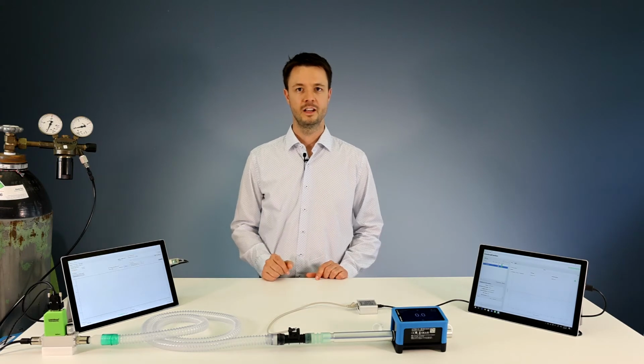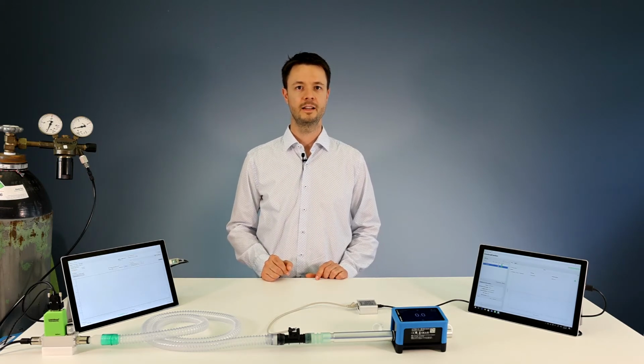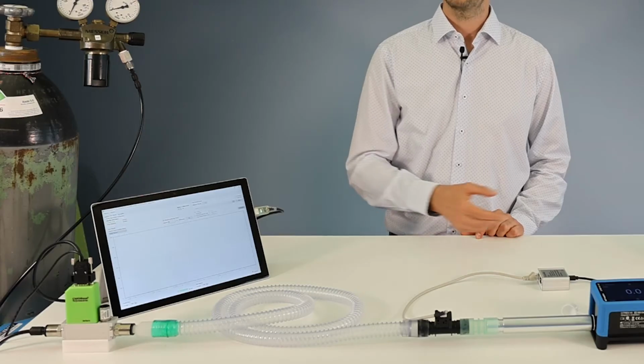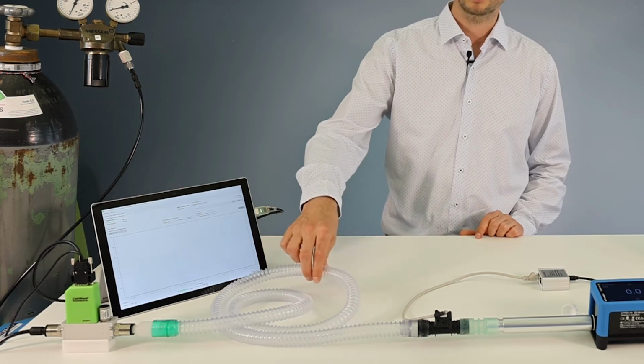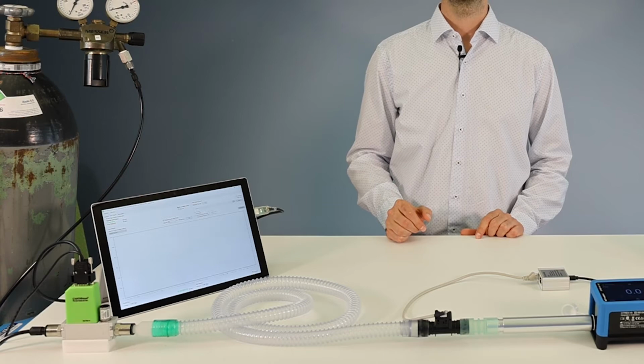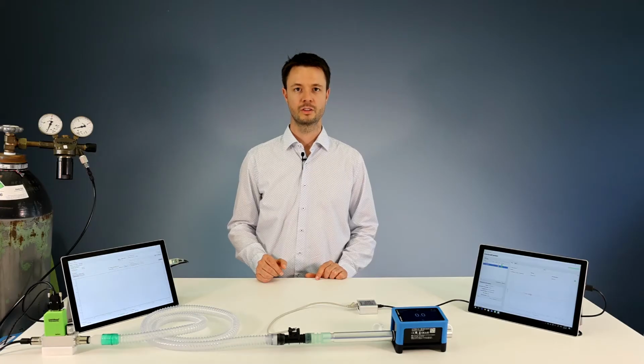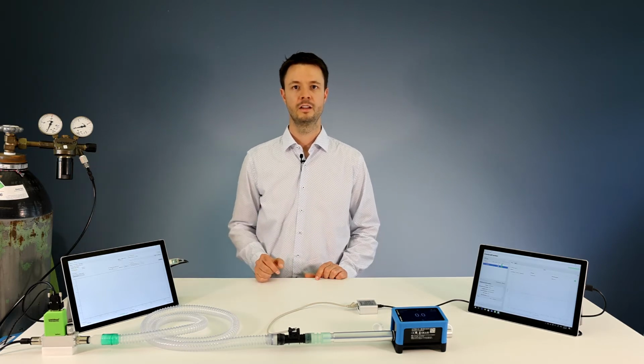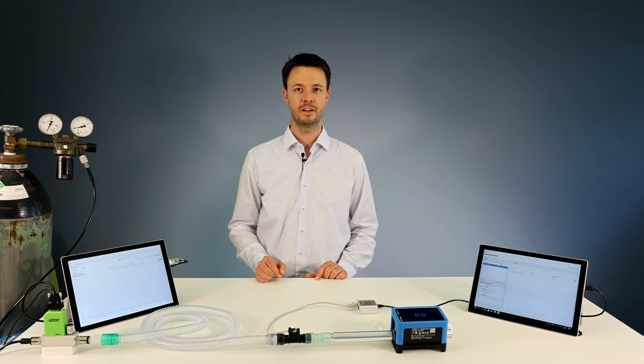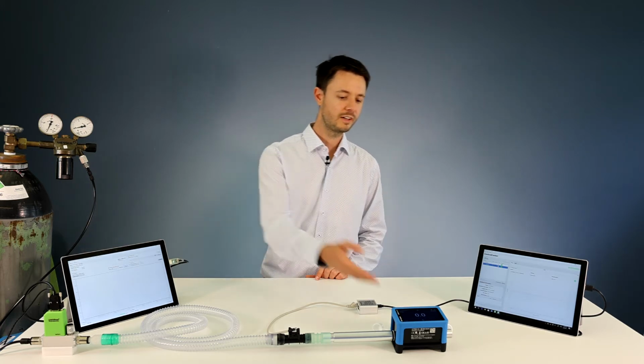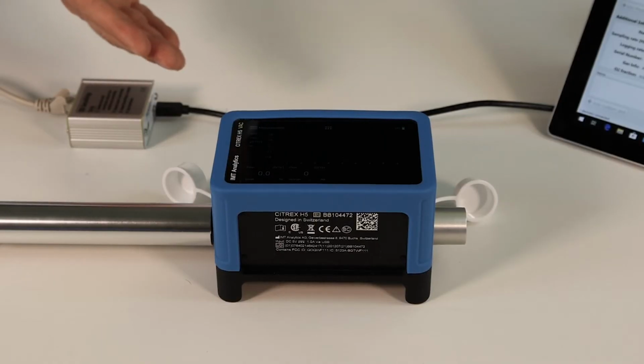After the flow sensor, we use a Citrex H5 device from IMT Analytics as our reference to verify the accuracy of the flow sensor. To connect these different devices, we like to work with medical breathing tubes, which allow easy and leak-tight connections. It is important to always compare flows at the same standard condition. Sensirion's flow meters output a flow in standard liters per minute, which is defined as the volume flow at ambient conditions of 1013 millibar and 20 degrees Celsius. On a Citrex H5 device, this corresponds to the setting 20/1013, which we'll select now.